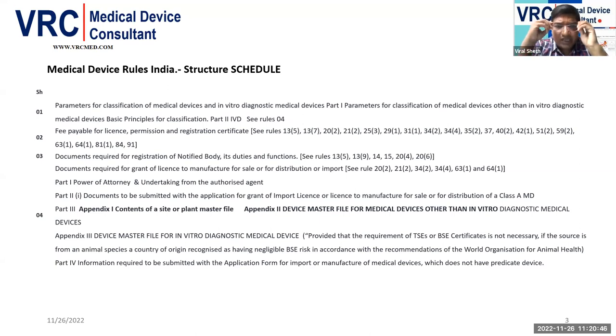So once we apply or submit the documents, if your device falls under class A and B, the notified bodies are supposed to do inspection of your premises and submit the reports to the CDSCO, and CDSCO then grants the license. So notified bodies have now become vital, becoming the bridge between the manufacturer and CDSCO.